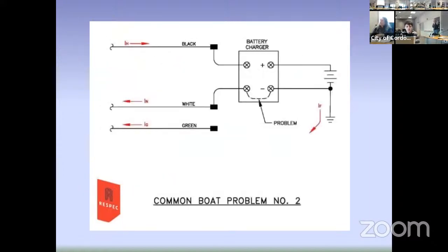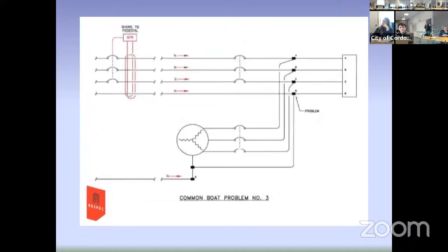But we're showing that in those instances where a battery charger, where the neutral conductor is connected through to the negative side of the battery, and the battery is connected to ground, then we'll have a ground current. This is an instance where a boat with a generator, and they're solidly connected to feed one or the other. In this instance, the neutral conductor on the generator should be bonded to ground for the safety on the boat. However, the problem comes about in that it ties into the ground on shore. The resolution to that that most boats are adopting is disconnecting the neutral when you're on shore power, disconnecting the neutral from the generator, and then that will prevent that circulating current.